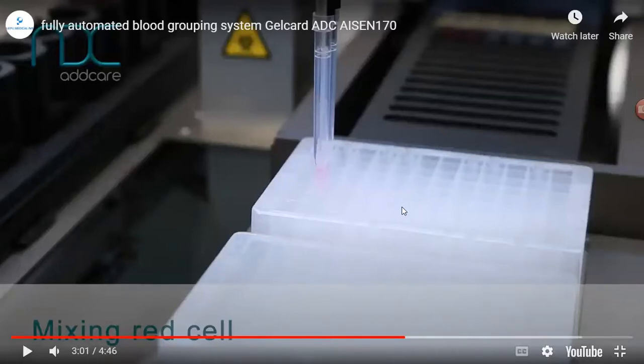The way they design automated equipment is they try to follow a manual process. They follow the manual steps and then combine all of this. Sometimes they have to stop the process for what we call incubation periods. The whole thing could be stopped in the process for the incubation. They have a mixing red cell here. If they mix the red cell, they can mix into some of this reservoir. Then from this reservoir, with computer tracking, they can move into some of these empty wells for the next testing process.